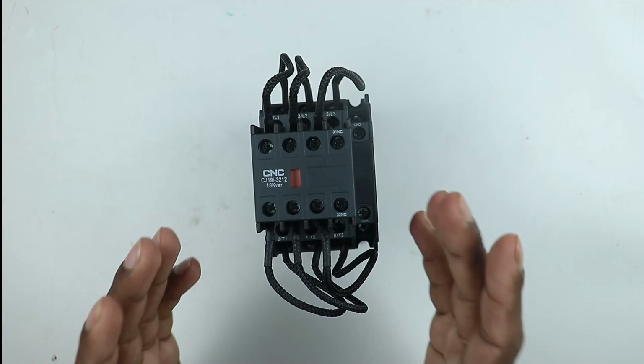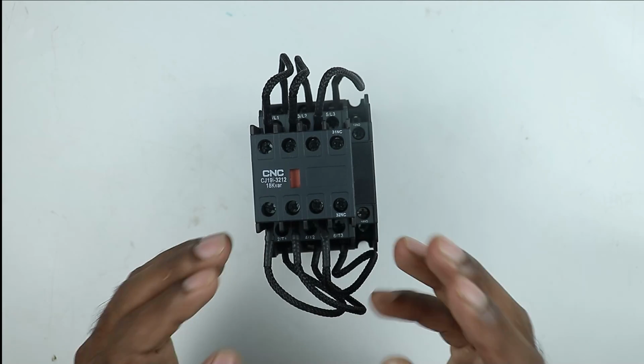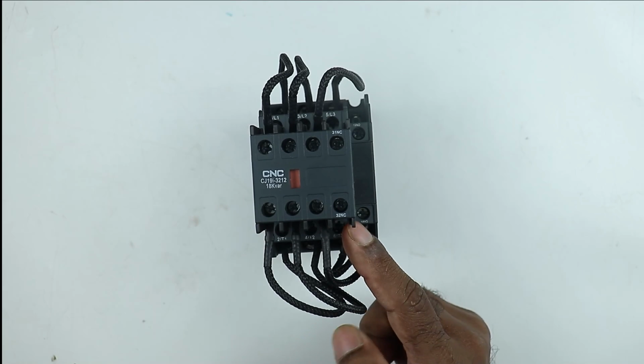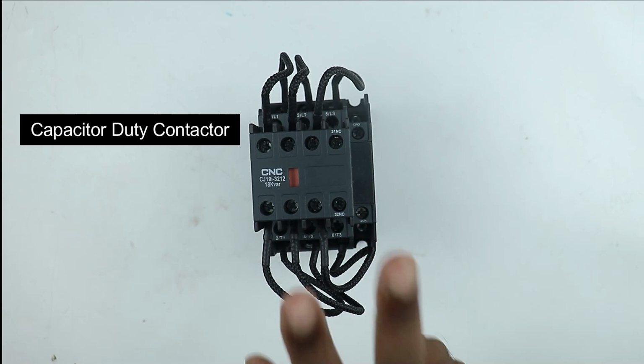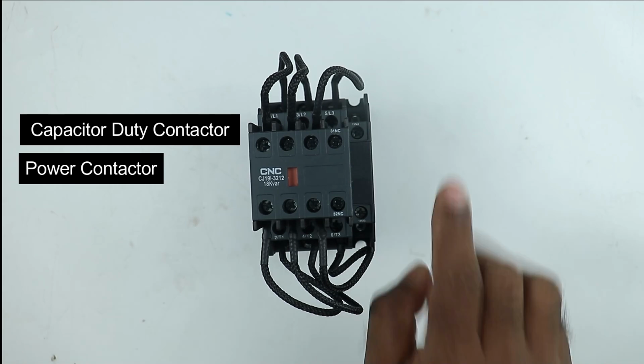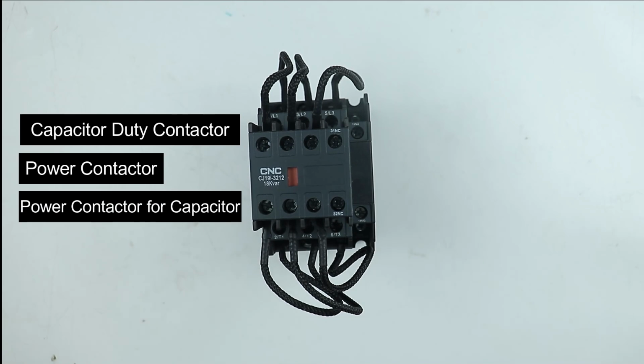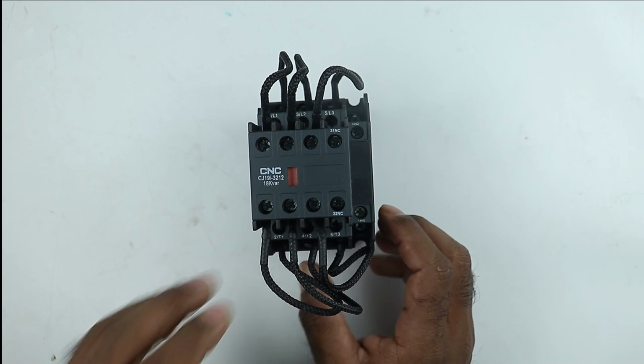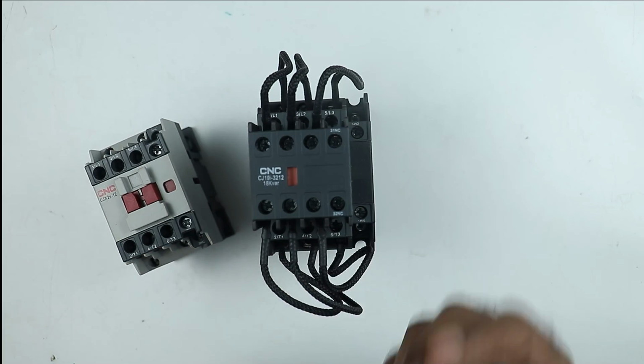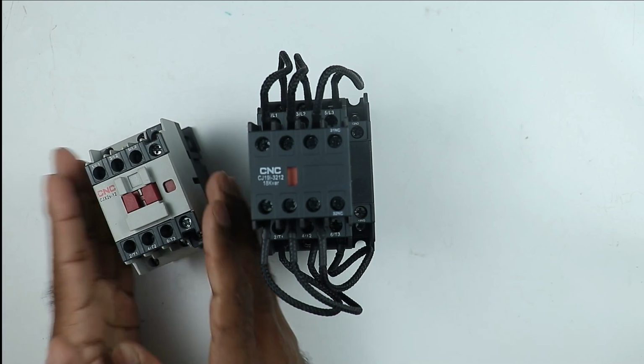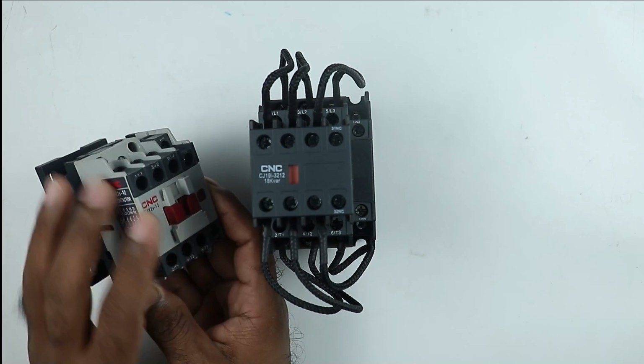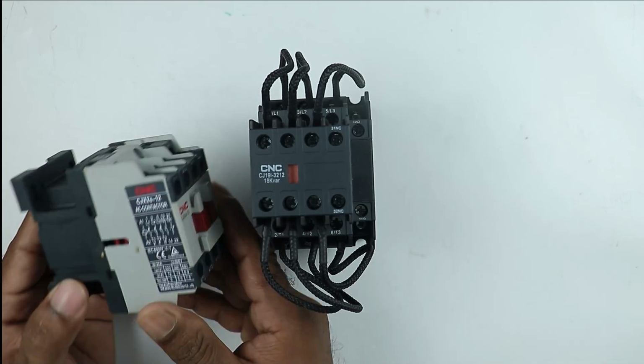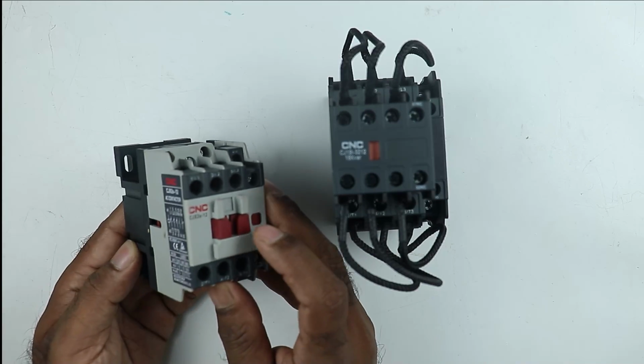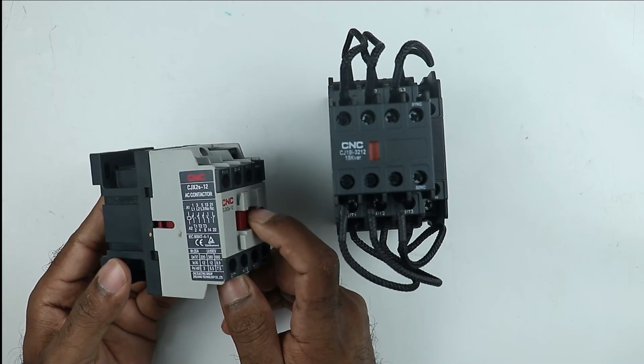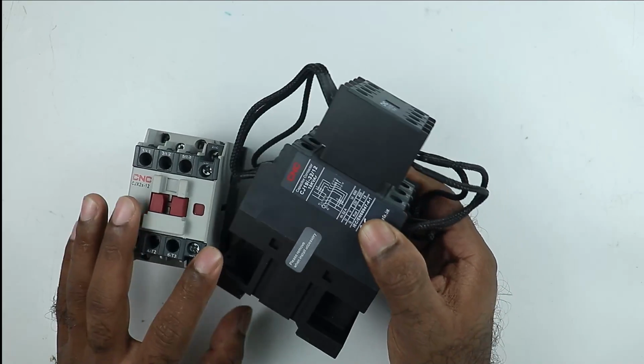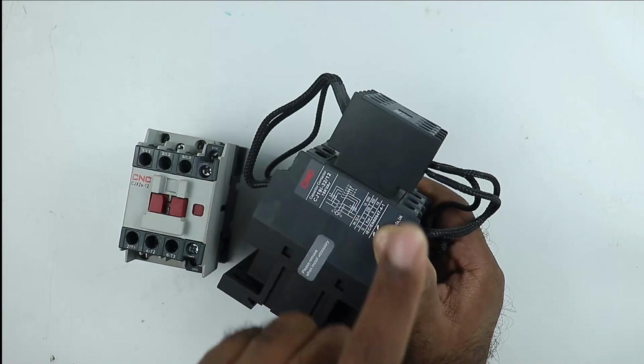Friends, let us first talk about this contactor. We know this contactor by three names. First one is duty capacitor contactor, second name is power contactor, and the third name is power contactor for capacitor. In which terms it is different from the normal contactor, let's understand. On this normal contactor, nothing is placed above it. It is a simple contactor to which we can provide electrical power supply for turning on and off. But in this power contactor, above the contactor, an add-on block is present.